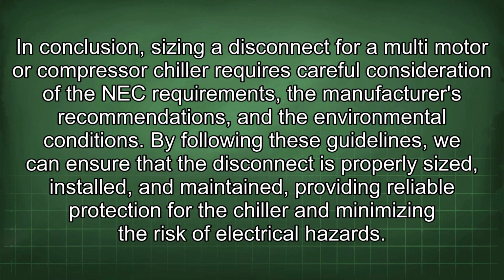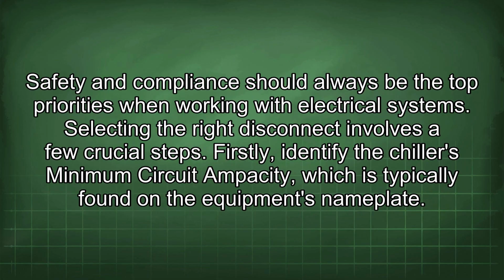In conclusion, sizing a disconnect for a multi-motor or compressor chiller requires careful consideration of the NEC requirements, the manufacturer's recommendations, and the environmental conditions. By following these guidelines, we can ensure that the disconnect is properly sized, installed, and maintained, providing reliable protection for the chiller and minimizing the risk of electrical hazards. Safety and compliance should always be the top priorities when working with electrical systems.